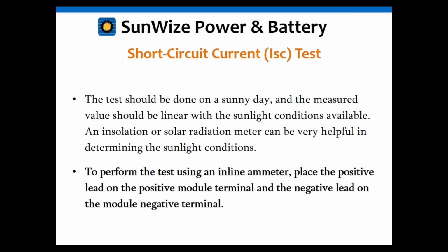As I mentioned before, tests should be done on a sunny day. Again, I prefer an inline meter. People have asked me before if you could do it with a clamp-on probe. The problem is you still need to make that short circuit somehow in order to get that current to flow. So you still need to have a shorting wire for that reason. So I find it just easier to do an inline.